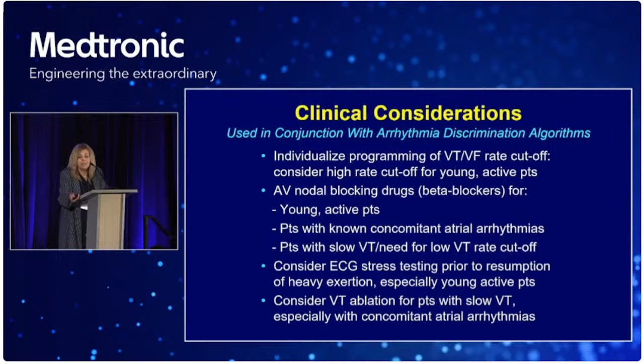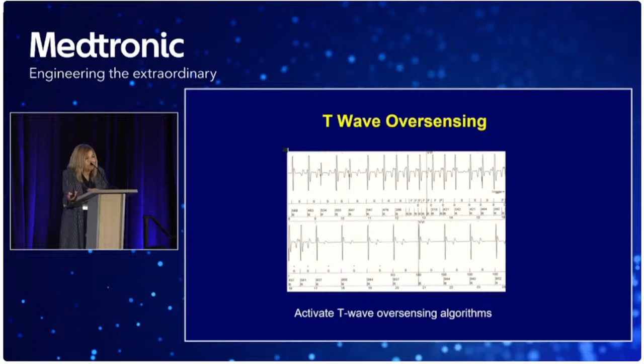There's also, sometimes we've seen trouble with T-wave oversensing. This is not only intermittently detecting the T-wave, and you can see it's a big T wave in this case, and you're counting that. So this one didn't get therapy, but in the Medtronic devices you do have a T-wave oversensing algorithm that looks different to our eye, and the engineers figure out how to make the device not see that, right?